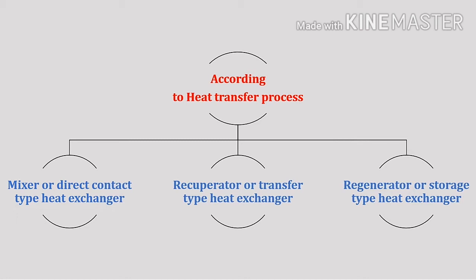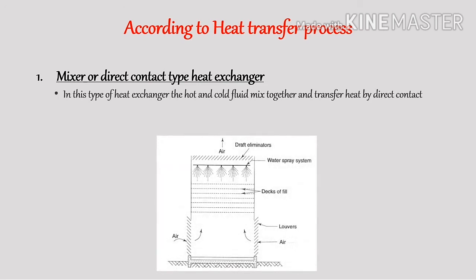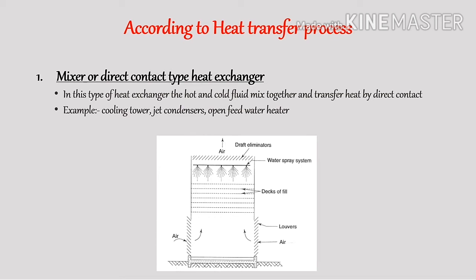The first type is the mixer or direct contact type heat exchanger. In this type, the hot and cold fluids mix together and transfer heat by direct contact. Hence there is simultaneous mass transfer and heat transfer. This type is used where mixing between the fluids is either desirable or harmless. Cooling tower, jet condenser, and open feed water heater are examples. The figure shows a cooling tower, which is one type of direct contact heat exchanger.